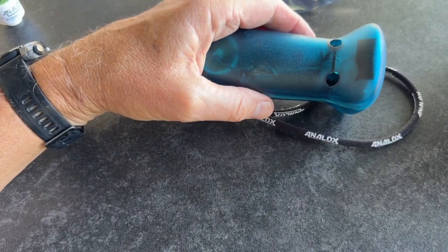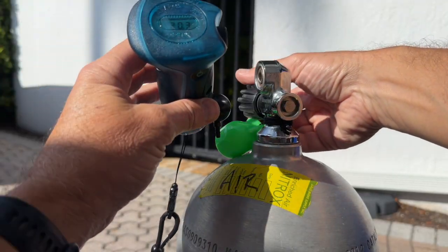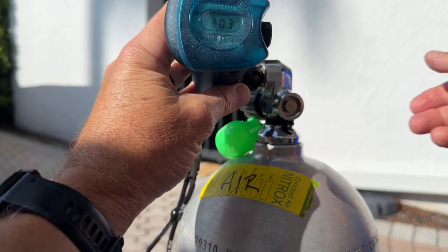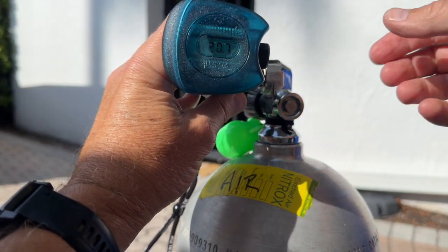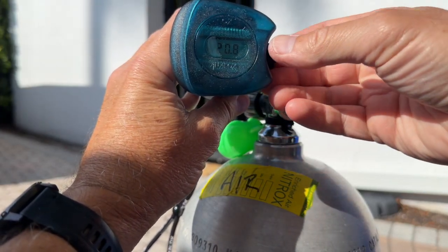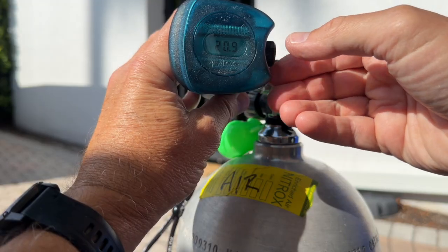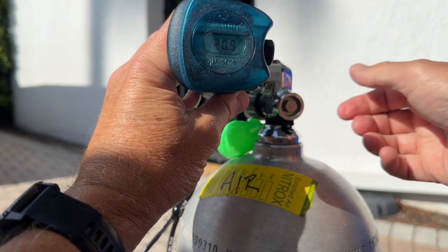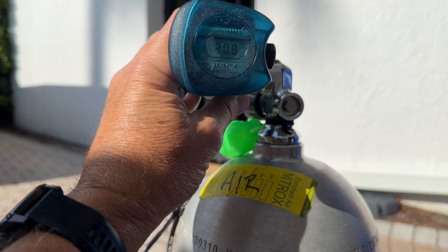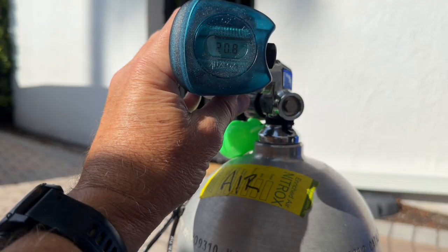Let's go test it out. So let's calibrate this. This is a known air source - I know this tank has pure air in it. Let's get this knob calibrated to 20.9, and then we'll test this out on another tank.